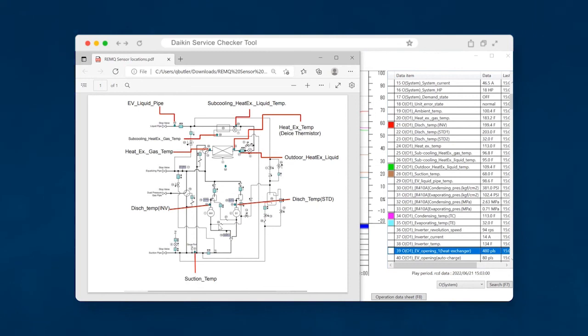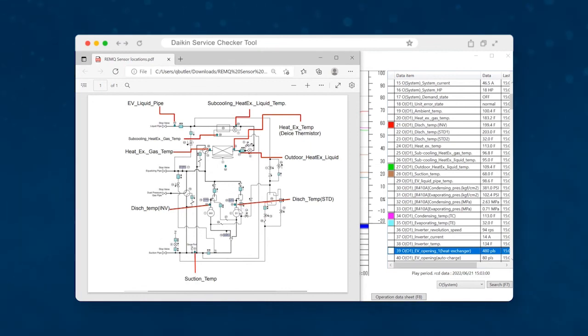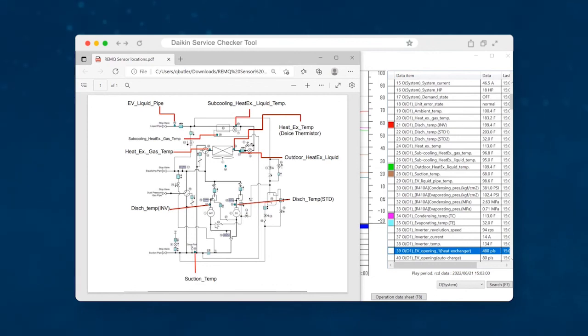It's another good way to check oil flow. We talked about oil flow. So if you wanted to confirm that you have adequate oil flow, you need to measure before and after wherever that oil is injected. So on this one, the oil separators are directly beyond the compressors. And you notice that there's a little line coming off the bottom of that separator that goes into the opposing compressor. So if we wanted to judge if this oil separator strainer was plugged, a couple of things we could do. One of them would be measure across the strainer. You should have no more than three degrees. And then we could also measure before and after where the oil enters into the suction line of the compressor. Notice this little squiggly line right here, that's a capillary tube. So that's just to ensure that we're not just dumping a quarter inch of discharge gas essentially into the compressor, but we're trickling oil into the suction line. So you should have a temperature difference of at least nine degrees before and after the injection of that oil.